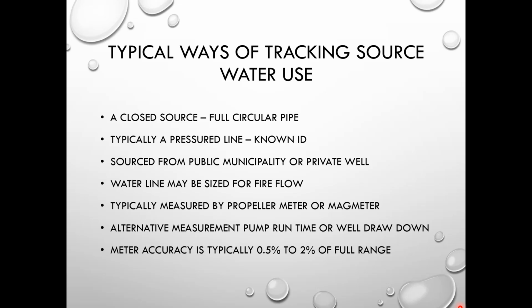Now, your meter accuracy when it's a full pipe, because generally these meters are just reading velocity, right? So these meters run off the continuity equation, which is basically the rate of flow equals the average velocity times the flow area. Well, since the area is known, in a truly full pipe flow meter, all we're doing is reading velocity. So it's really just one sensor, and as long as they're pinned down, they'll run at a much better accuracy range of 0.5% to 2%.